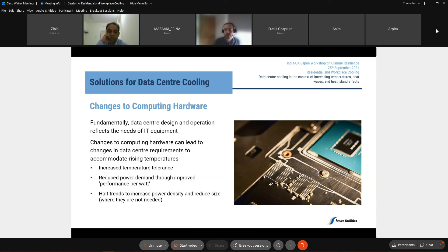Manufacturers claim there's market demand for this trend, but increased power density and reduced form factor can make higher temperatures in air-based cooling much less viable. Avoiding this will make it easier for existing cooling systems to support new IT equipment, avoiding the need to replace the cooling systems.